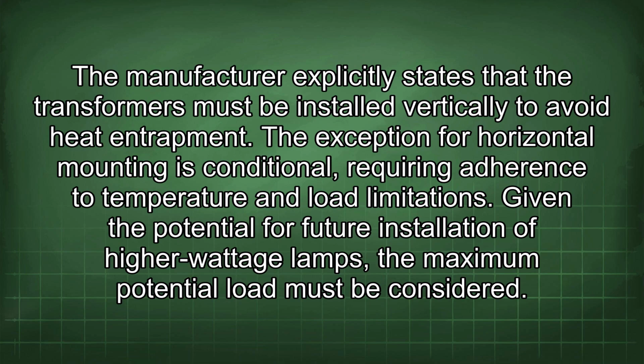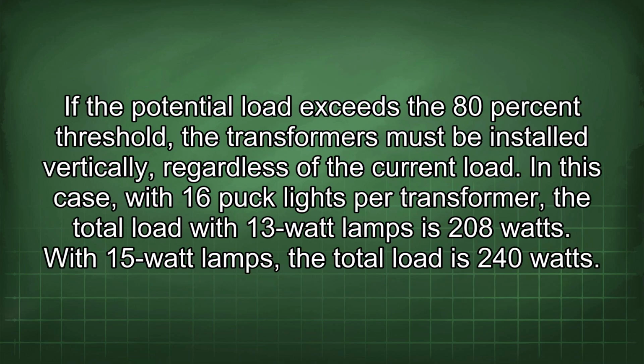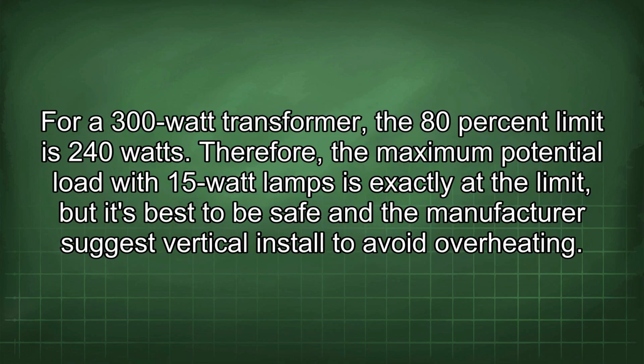Given the potential for future installation of higher wattage lamps, the maximum potential load must be considered. If the potential load exceeds the 80% threshold, the transformers must be installed vertically, regardless of the current load. In this case, with 16 puck lights per transformer, the total load with 13-watt lamps is 208 watts. With 15-watt lamps, the total load is 240 watts. For a 300-watt transformer, the 80% limit is 240 watts. Therefore, the maximum potential load with 15-watt lamps is exactly at the limit, but it's best to be safer and the manufacturer suggests vertical install to avoid overheating.